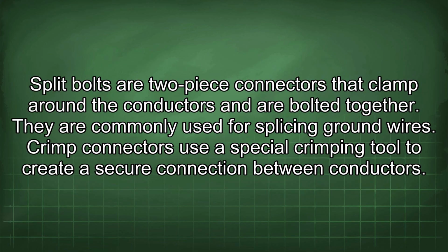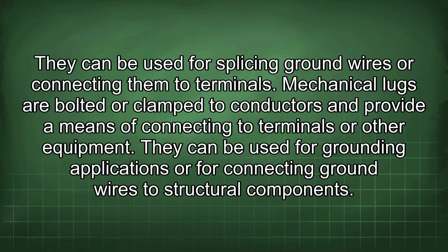Split bolts are two-piece connectors that clamp around the conductors and are bolted together. They are commonly used for splicing ground wires. Crimp connectors use a special crimping tool to create a secure connection between conductors. They can be used for splicing ground wires or connecting them to terminals. Mechanical lugs are bolted or clamped to conductors and provide a means of connecting to terminals or other equipment. They can be used for grounding applications or for connecting ground wires to structural components.